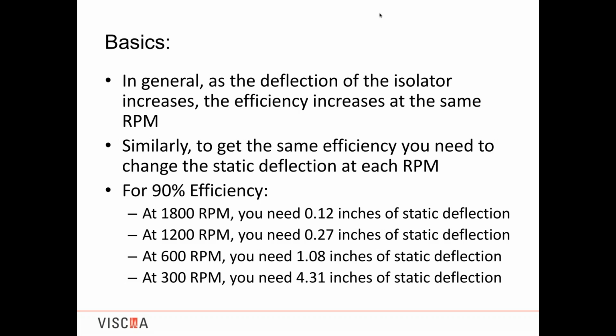You see if I'm shooting for 90% efficiency, if in this specification I need to get 90% efficiency, I need the RPM of the equipment. That's one of the most important numbers you have to start with. If the motor is running at 1800 RPMs, I'm only going to need 0.12 inches, roughly 1/8 of an inch. Not much, a block of rubber, a pad or something will give me that. But as I decrease my RPMs, if I get down to 300 RPMs, you see I need 4 inches of deflection just to get the same 90% efficiency.